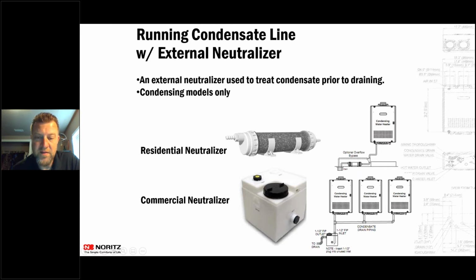So if you had this vertically versus horizontally like it is here in the picture, it could create a different trap inside of there, which I saw in a bunch of mod pizzas that we do a whole lot with up in the Pacific Northwest. And the contractor put that in and created a separate trap, so he kept getting condensate codes all the time. So once he added the vent, that went away.